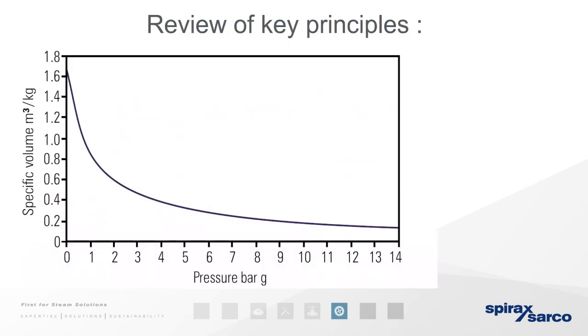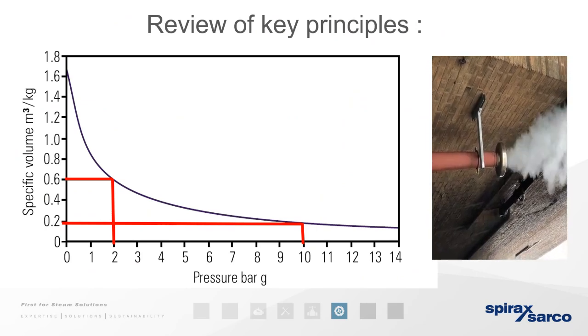So as we said, there is a link between pressure and temperature. In this particular case, 10 bar is just under 0.2 cubic meters per kilogram. If we lower the pressure, as you can see here for 2 bar, we've almost trebled the volume that the steam takes. So that's why when it comes to supplying steam around a system, until you get to the point of use, we try to maintain as high a pressure as possible, because it allows us to use the smallest pipework possible, which reduces costs. It's also about heat losses and things like that. So we should be only reducing pressure at point of use, so the last few meters effectively. And as you can see, we see a lot of venting otherwise.